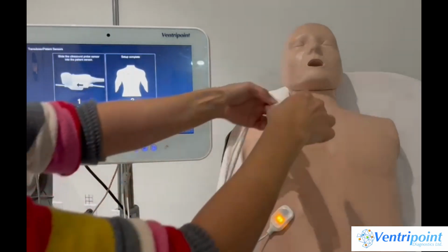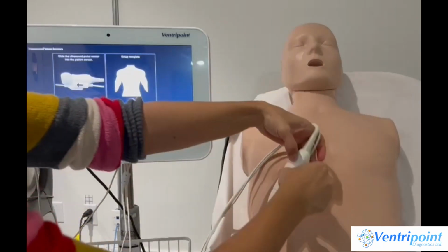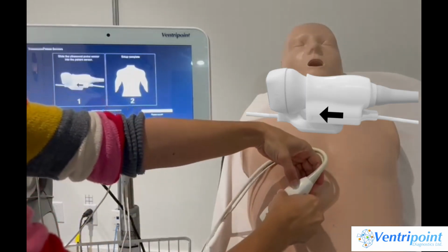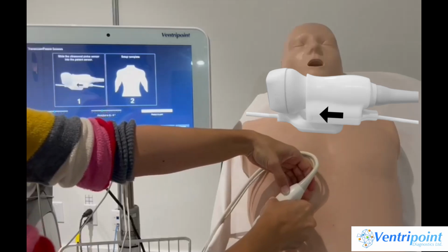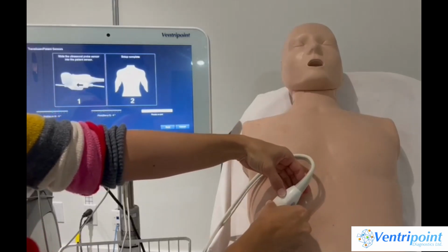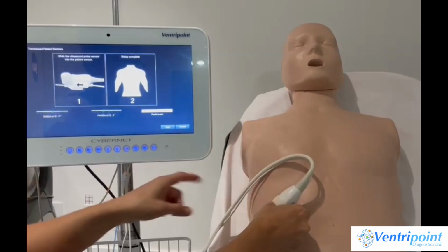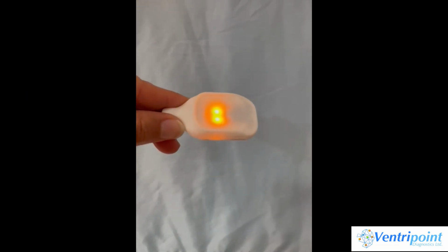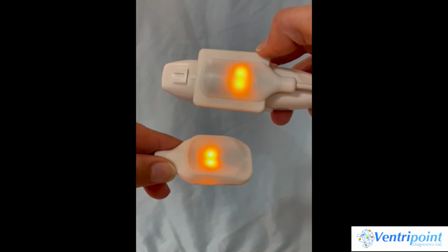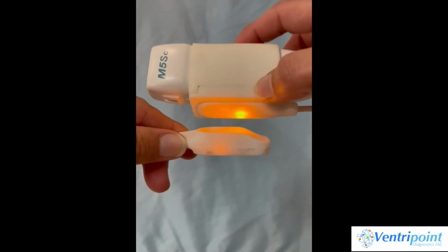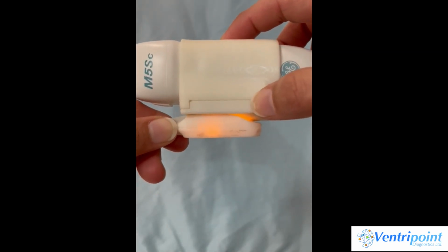Take your echo transducer and gently slide the domed area of the probe sensor into the convex depression on the patient sensor. You should feel a slight ridge when they are located correctly. Let's look at that process in detail. Rotate the probe sensor to align with the patient sensor. Then slide to locate correctly.